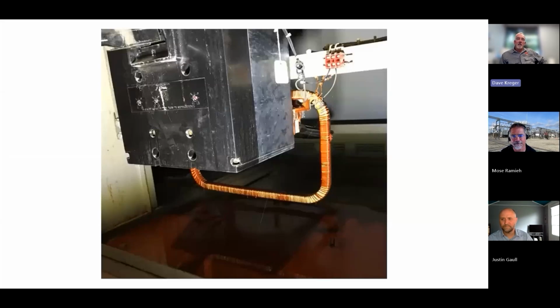If you open circuit a CT, you're going to cause some real problems here. And we see this actually more often than you would think, seeing that red goo at the bottom of a switchgear assembly. So obviously, ground fault protection is very important. We're talking about larger amounts of current, 1,200 amps and up, that's required to have ground fault protection according to the code. So huge issue here, both for personnel safety and for facility safety.